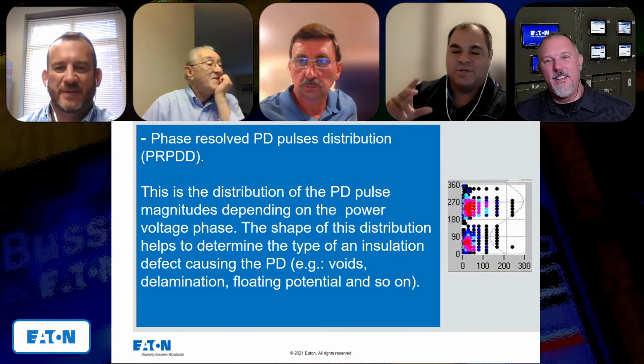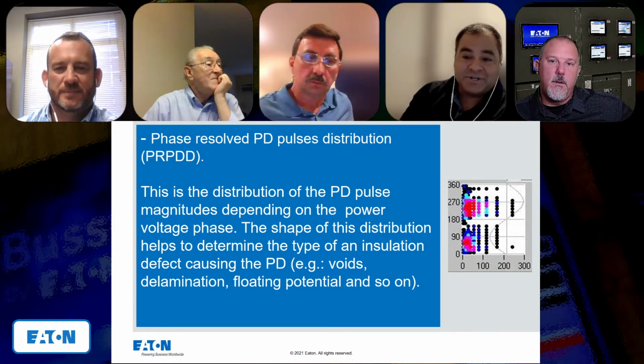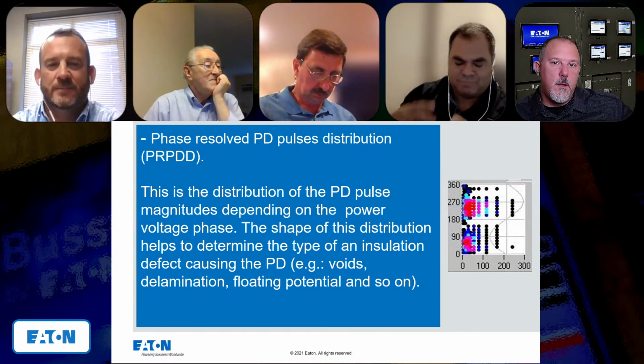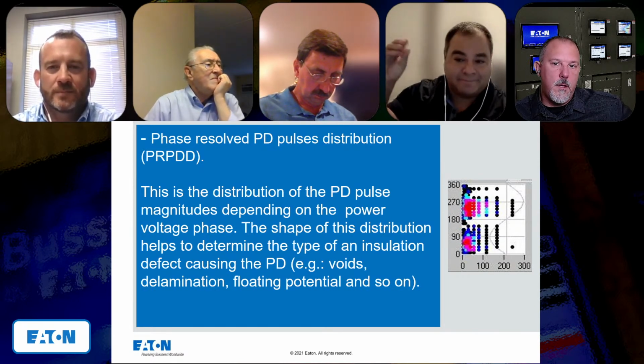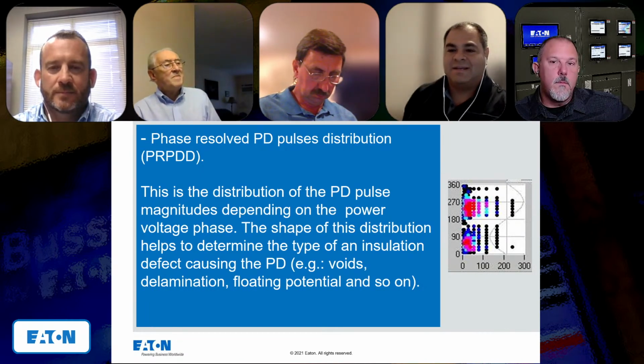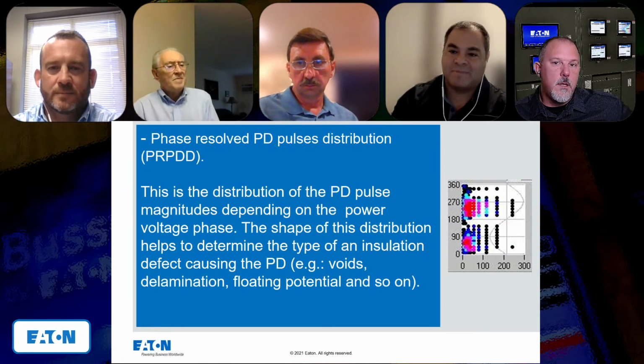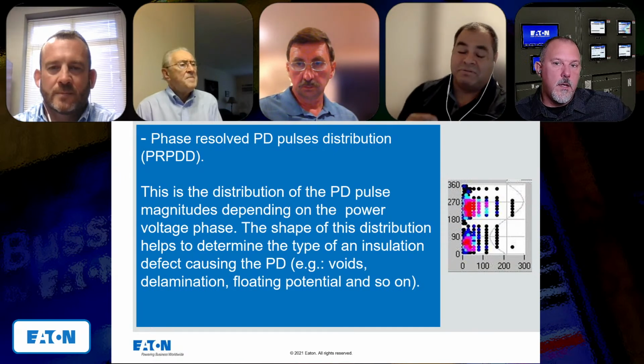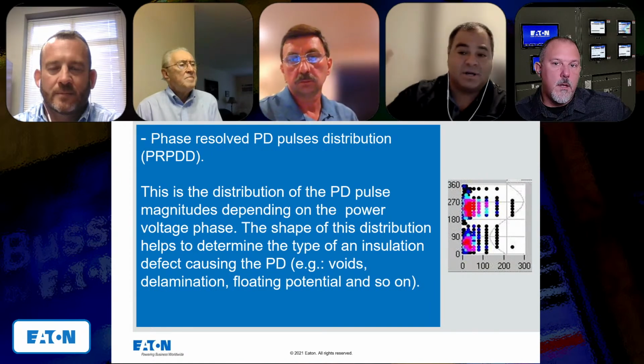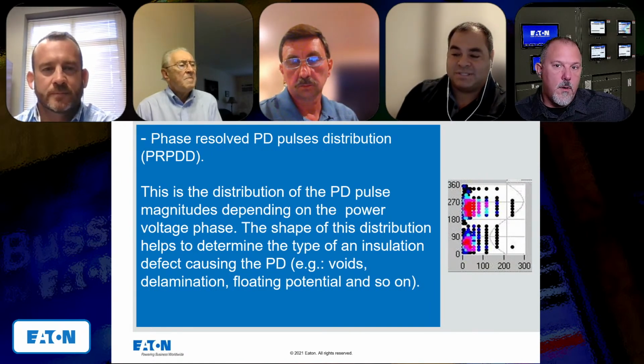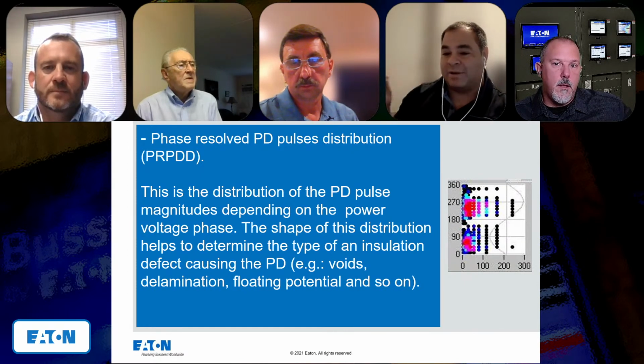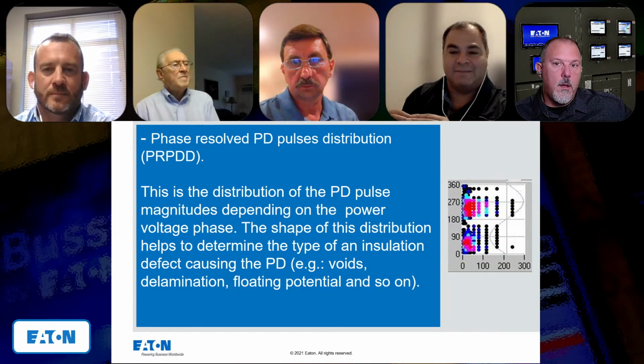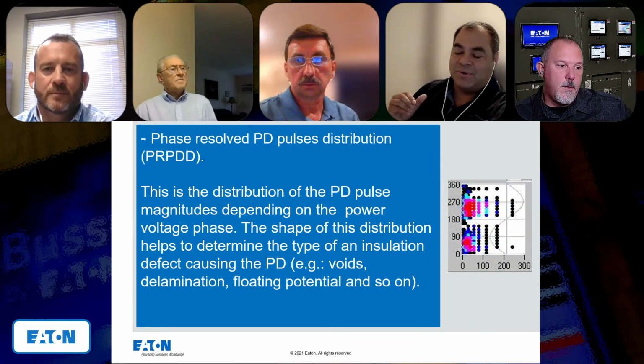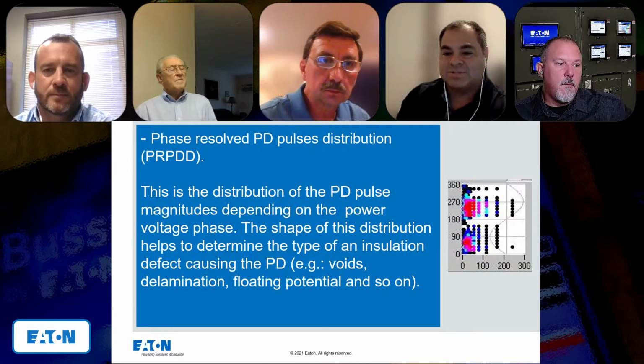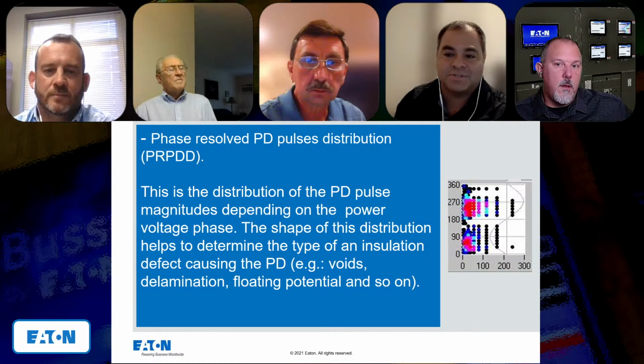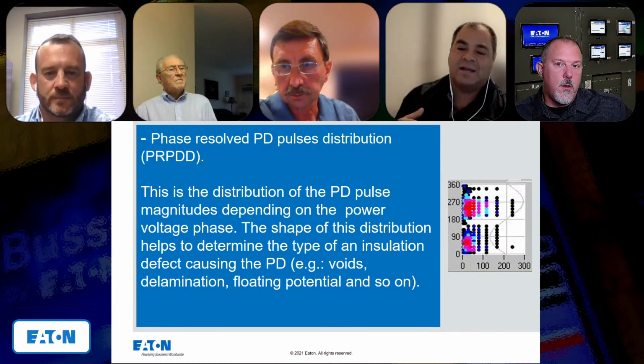Okay, Raul, so it is like a two-stage process. At the beginning, the equipment detects the partial discharge. It has an internal algorithm that processes it and assigns it to different channels, and you get an alarm on a small red LED. So the next step is to take a look at the information stored in the InsuGuard and see what happened. Because sometimes it could be real PD, for example, the bus duct getting humid, or sometimes it's switching of the breakers in other cubicles. That could get into the InsuGuard, confuse the equipment, and it shows the alarm. Or it could also be electrical noise coming from the ground. So you need to double check that it's real PD before taking any action. Gotcha. That's why it's not like a green or red. No, you need to take a look at the information.